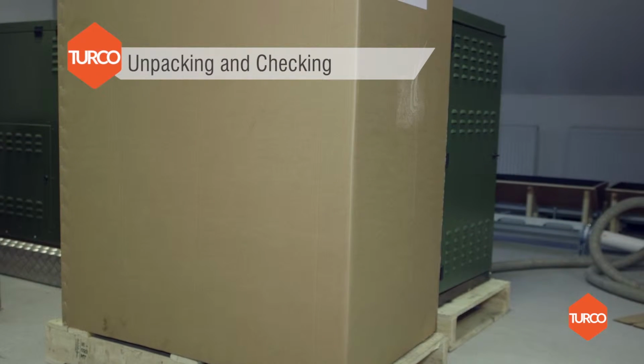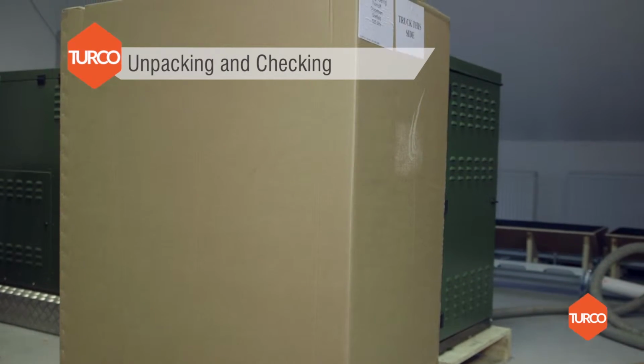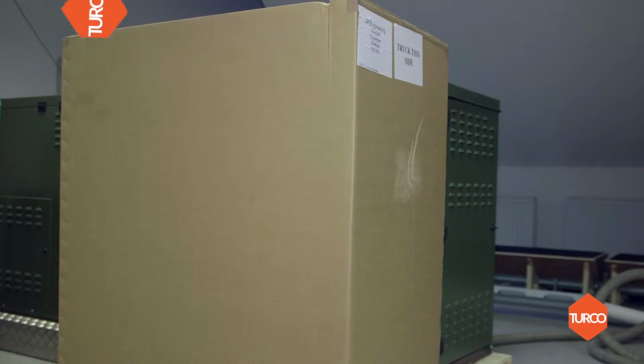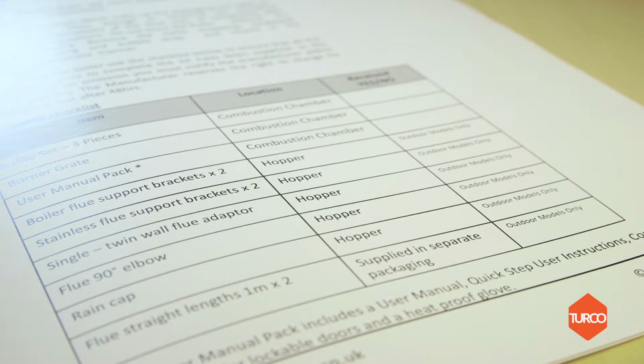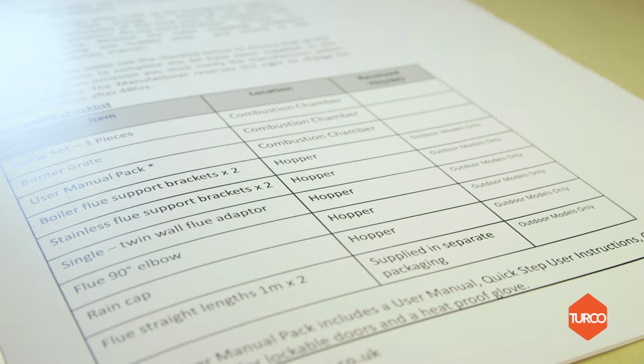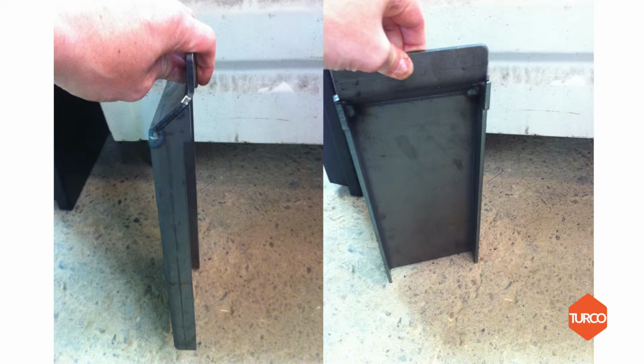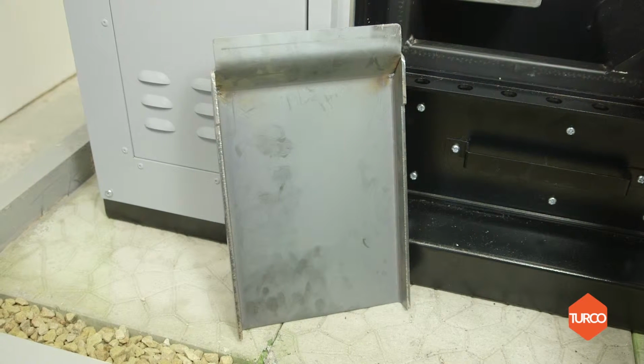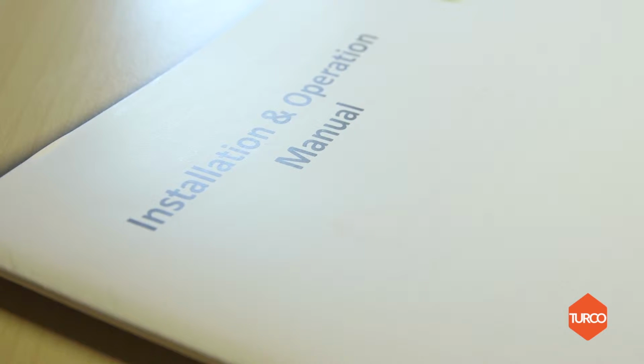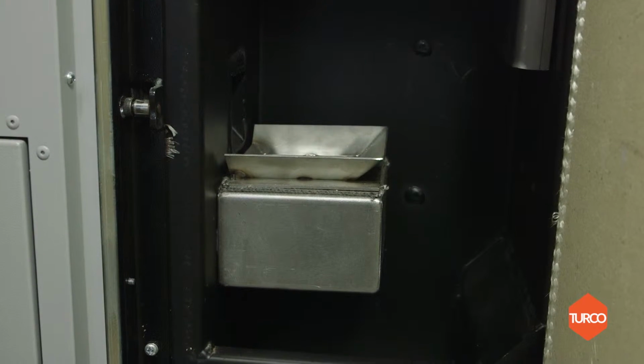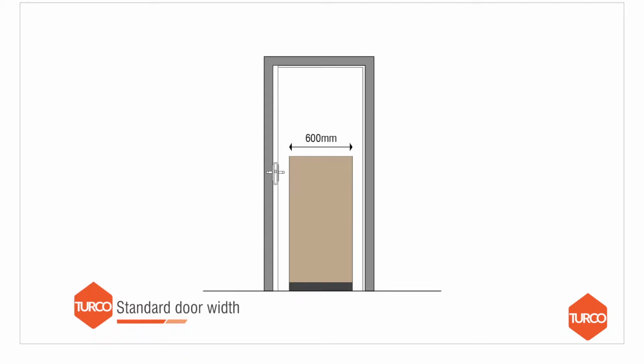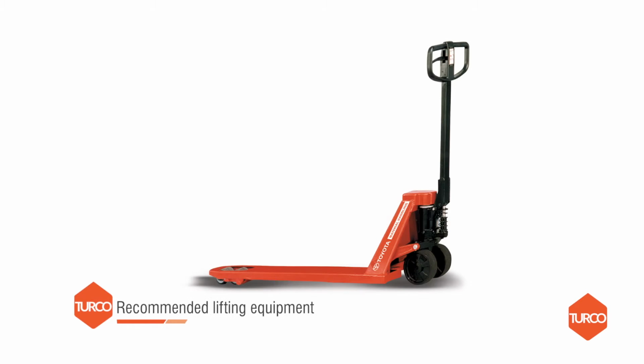Unpacking. Your Woodsman boiler is supplied on a single pallet and the materials which make up the packaging are 100% recyclable. Check the unpacking checklist in the manual to ensure you have all the required components. For example, 2 baffle plates on a 28 kilowatt boiler, 1 baffle plate on 16 kilowatt models, user manual pack, burner grate, etc. All Woodsman domestic boilers are designed to fit through a standard door width. However, they do need careful handling and you will need manual handling equipment. For example, the 28 kilowatt model weighs almost 200 kilograms.